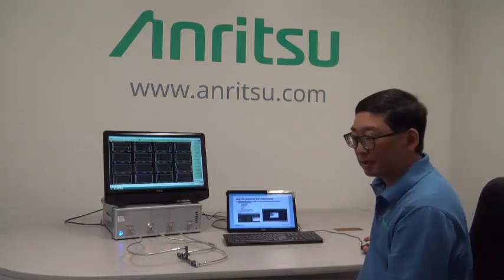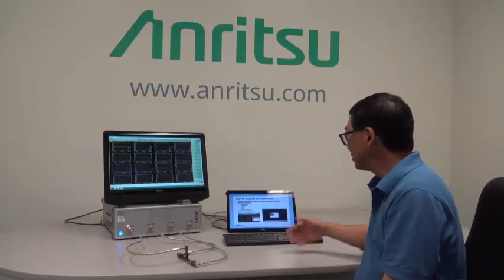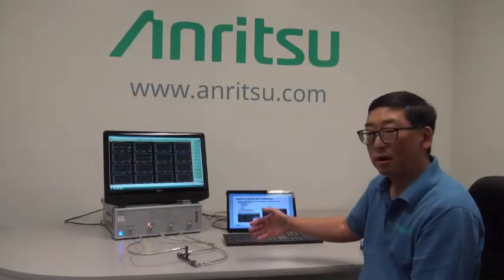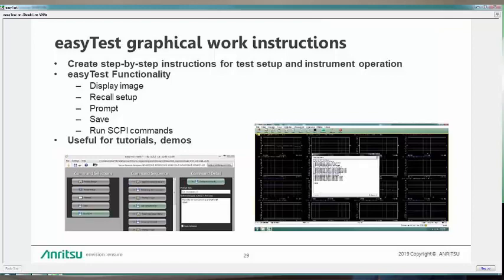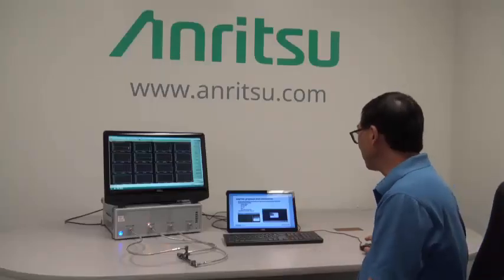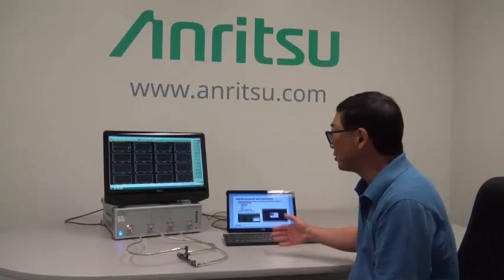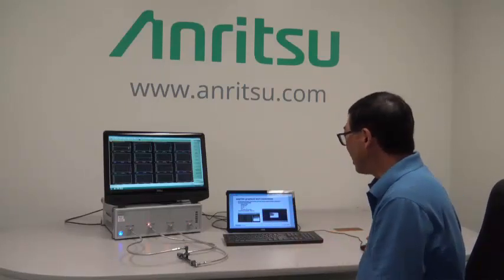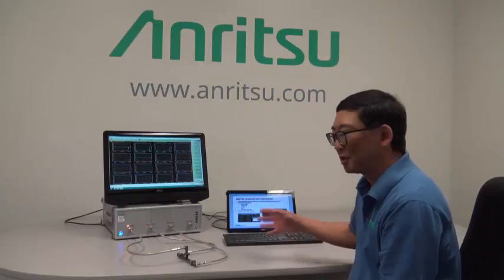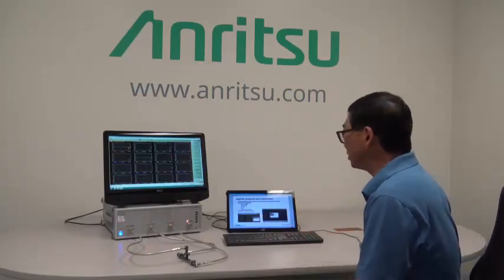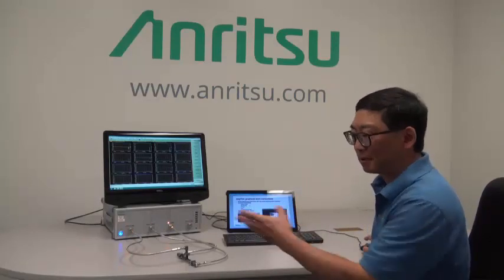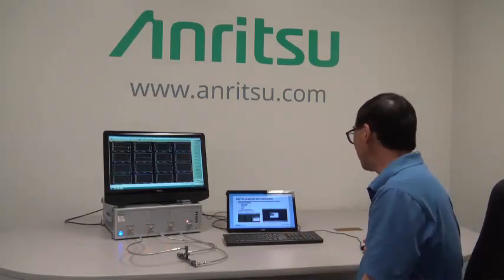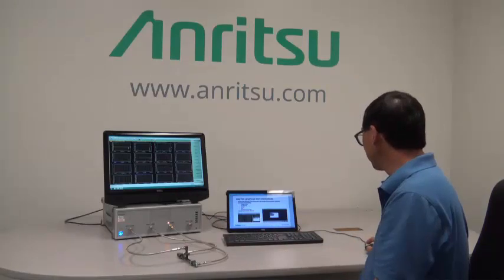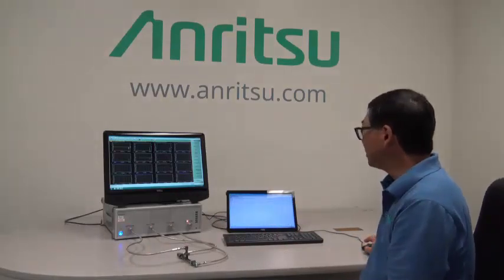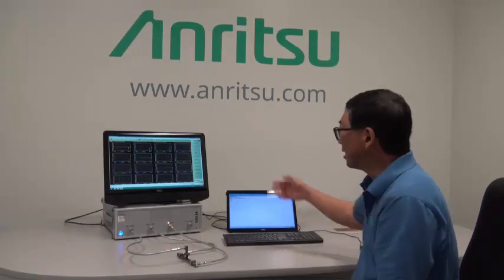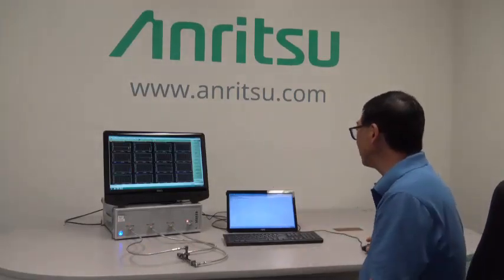Graphical work instruction using easyTest has the ability, as I mentioned, to do different steps: display image, recall setup, prompt the user, save data, or run SCPI instructions. It's useful for tutorials, demos, and work instructions. It allows expert users to share their knowledge easily by doing a graphical instruction that can be easily sent to other users. So here we have our first SCPI instruction.